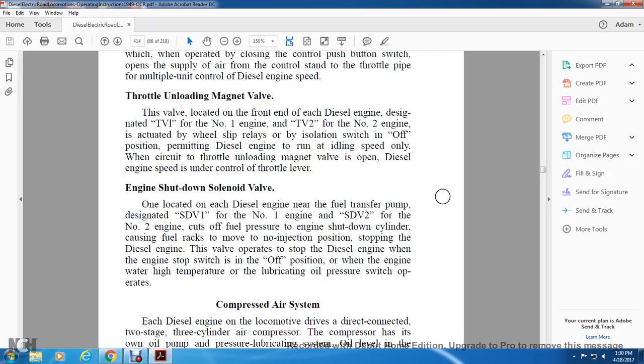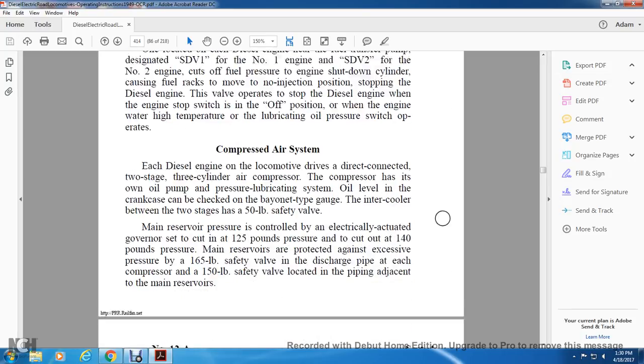One is located on each diesel engine near the fuel transfer pump, designated SDV1 for the number 1 engine and SDV2 for the number 2 engine. It cuts off the fuel pressure to the engine shutdown cylinder, causing the fuel racks to move to the no injection position, stopping the diesel engine. The valve operates to stop the diesel engine when the engine stop switch is in the off position, or on high water temperature or low lubricating oil pressure.